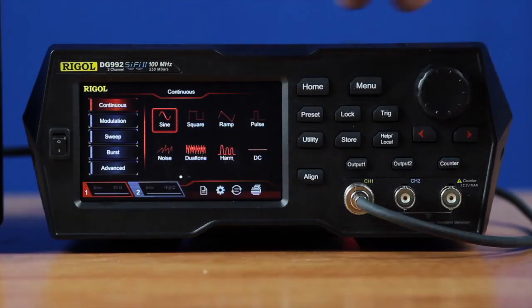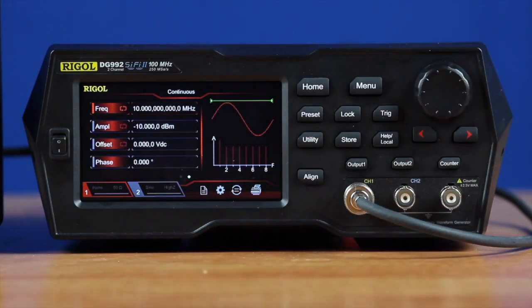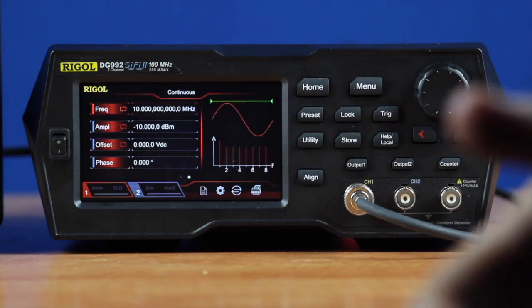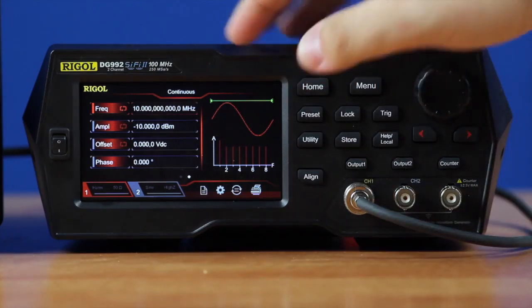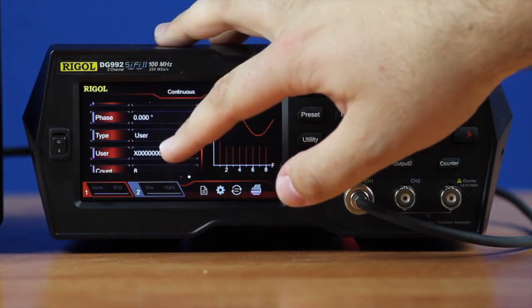To enter this, go into the continuous menu and then press on the harmonic function. I've already set the first harmonic to be at 10 megahertz with an amplitude of negative 10 dBm. You can also choose the offset and phase of the first harmonic.